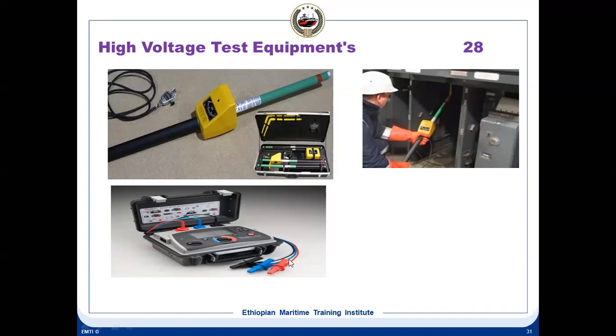In this megger you will find three wires. A normal megger has only one positive and one negative. Here you will find one more wire. You see the blue one? This is called the guard terminal, in addition to positive and negative. So you have a positive, a negative, and a guard terminal. The guard wire is used to drain any surface leakage current, because of moisture.